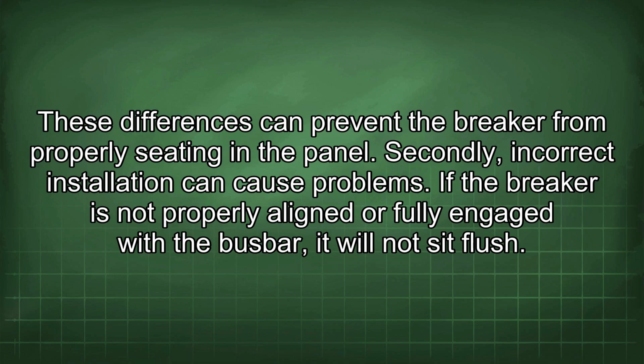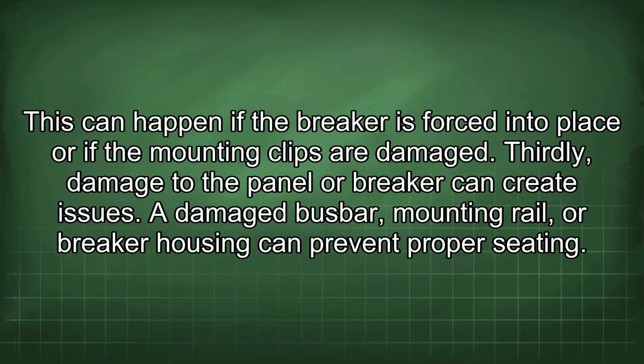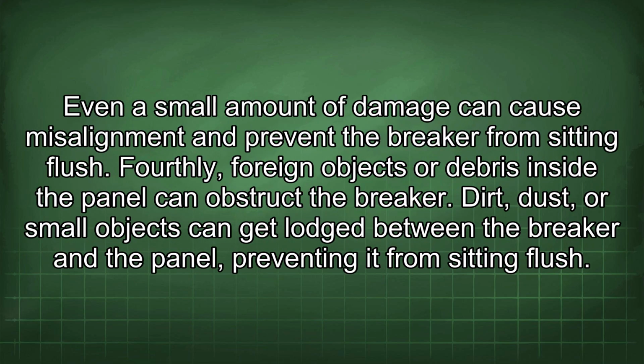Secondly, incorrect installation can cause problems. If the breaker is not properly aligned or fully engaged with the bus bar, it will not sit flush. This can happen if the breaker is forced into place or if the mounting clips are damaged. Thirdly, damage to the panel or breaker can create issues. A damaged bus bar, mounting rail, or breaker housing can prevent proper seating. Even a small amount of damage can cause misalignment and prevent the breaker from sitting flush.